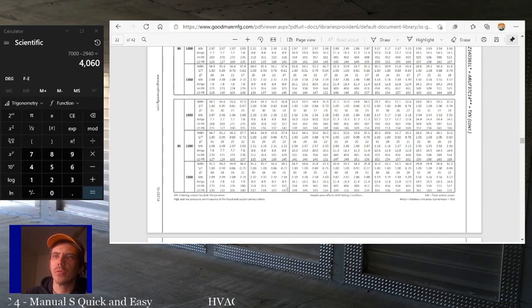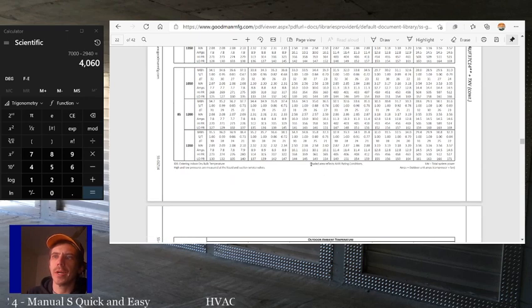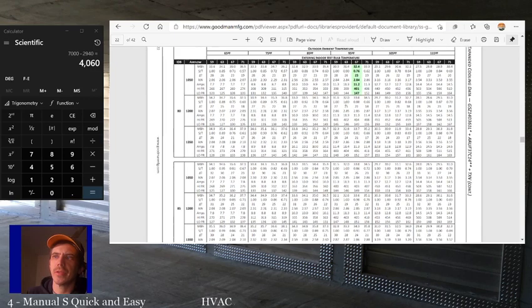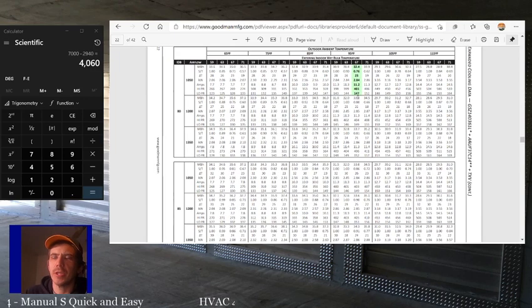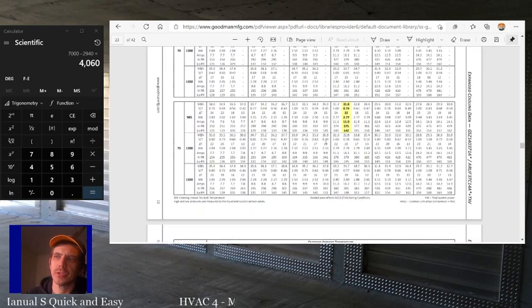For most equipment, all the numbers are at AHRI rating conditions. So this is how they determine the efficiency of the equipment. 80 degrees inside, 67 degrees wet bulb, so that's 80 degrees at 50% humidity, and at 95 degrees outside. These are how they determine the efficiency of the equipment. These are not what you use for your load calculation.